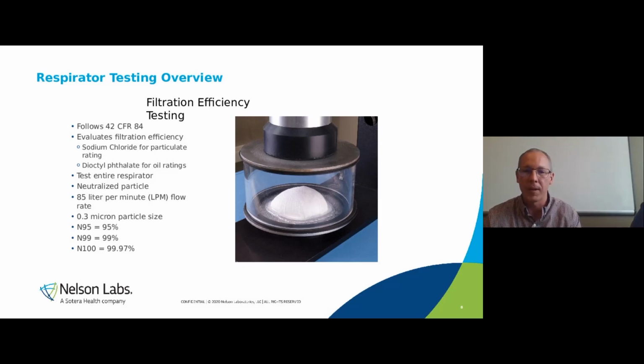We do test the entire respirator. As you see in the picture, the entire respirator is mounted to a test plate and placed into the test apparatus. The particles that are being challenged to the device are neutralized, meaning that the normal charge on that particulate is being taken off. That reduces the ability of the mask to use electrostatic filtration aspects, which would aid in the filtration. So really what this test is looking at is the actual impact filtration of the respirator. The flow of the air going through the respirator is 85 liters per minute, and the mean particle size of the sodium chloride or the dioctyl phthalate is 0.3 microns in size.